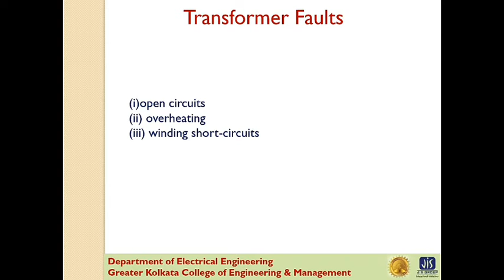Winding short circuits are called internal faults on the transformer. They arise from deterioration of winding insulation due to overheating or mechanical injury. When an internal fault occurs, the transformer must be disconnected quickly from the system because a prolonged arc in the transformer may cause oil fire. Therefore, relay protection is absolutely necessary for internal faults.